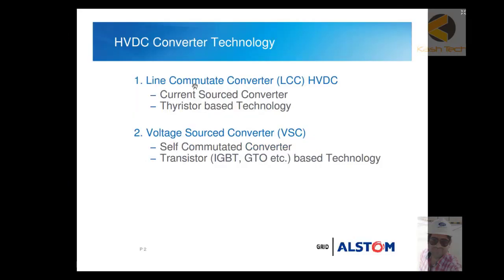Here is a comparison between voltage source converters (VSC) and line commutated converters (LCC) for HVDC stations. Line commutated converters are current source converters based on older thyristor technology. The newer technology, first introduced by ABB, is voltage source converters. VSCs are light in weight, economical to use, and are self-commutated converters using IGBT and GTO transistor-based technology.